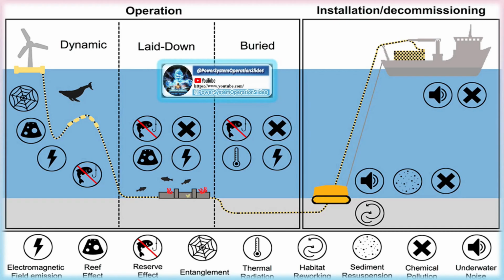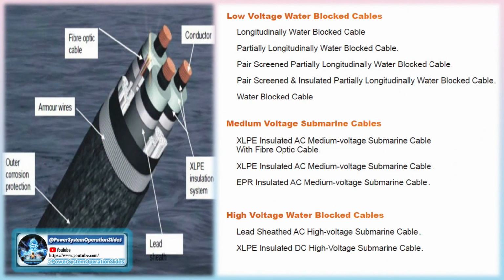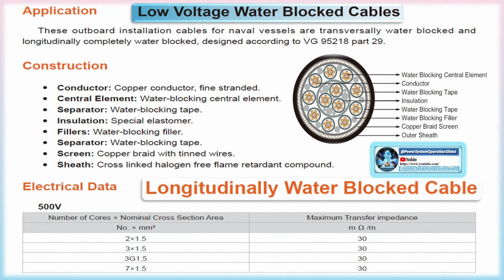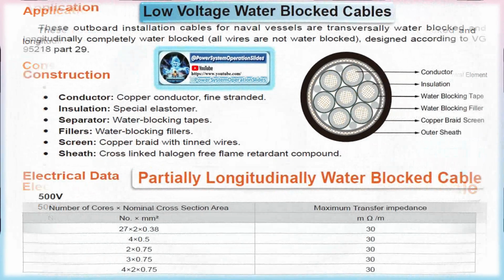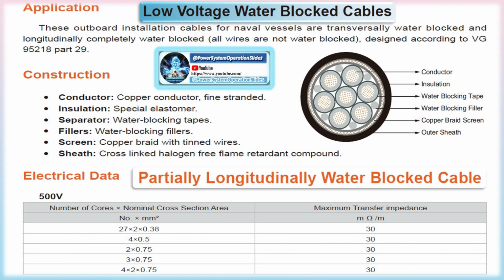Water-blocking tape barrier: multiple layers of water-blocking tapes or swelling powders are applied to provide additional protection against water ingress. These materials absorb water and swell to seal any potential leaks, ensuring the cable remains dry and operational. Armor material: galvanized steel wires or sometimes aluminum are used to armor the cable. The steel armor provides mechanical protection from external forces such as fishing nets, anchors, undersea currents, and seabed movement. The armor is essential in protecting the cable from mechanical damage during installation and operation. The choice of material for the armor depends on the depth of the installation and the expected mechanical stresses.